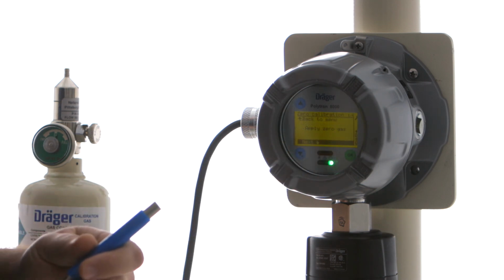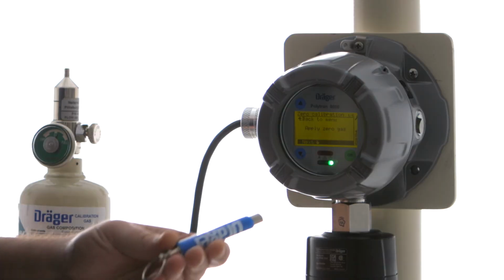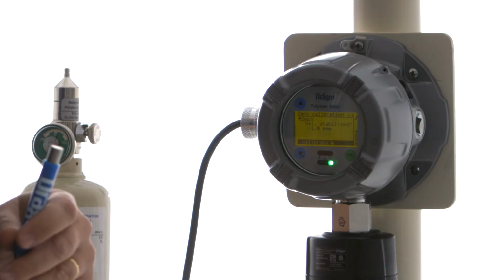So now it's telling us to apply zero gas. If we were to have a cylinder, we would now turn our cylinder on. Since we're doing a fresh air calibration, there's really nothing to turn on. Just one note, if you are doing a fresh air calibration, just make sure the area does not contain any carbon monoxide or any other cross-sensitive gases at the time. So we're going to hit next.